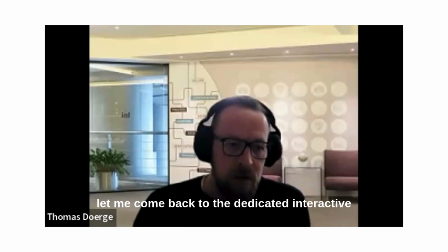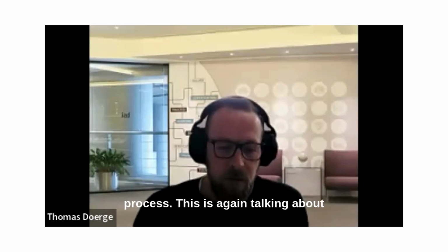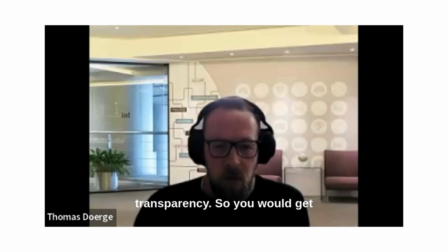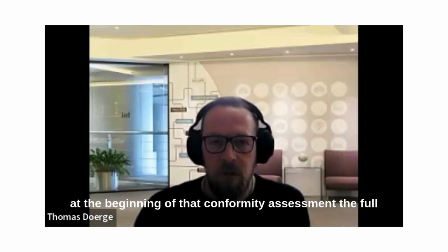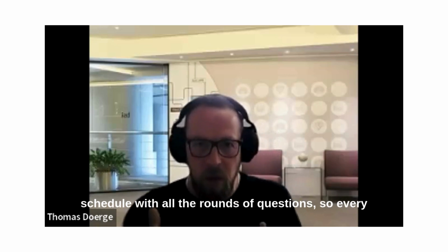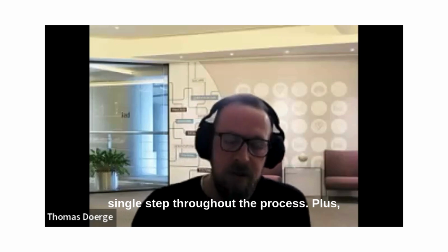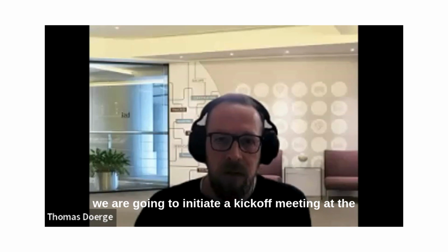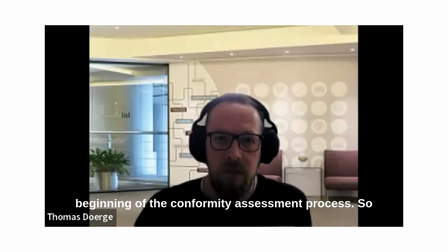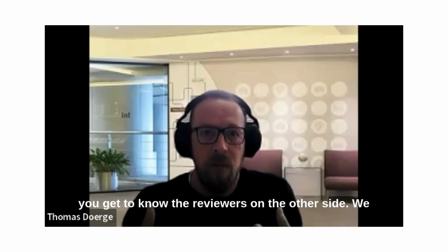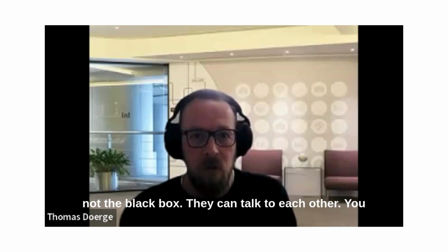So let me come back to the dedicated interactive process. This is again talking about transparency. You would get at the beginning of that conformity assessment a full schedule with all the rounds of questions, so every single step throughout the process. Plus, we are going to initiate a kickoff meeting at the beginning of the conformity assessment process, so you get to know the reviewers on the other side. We are not a black box. They can talk to each other.